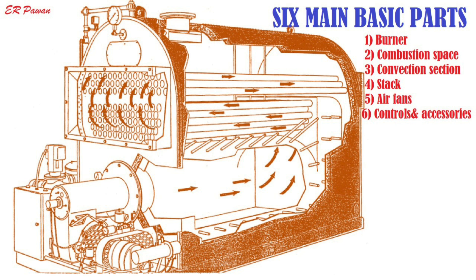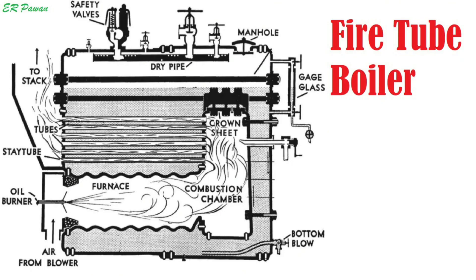Let's start with the fire tube boiler. Hot flue gases flow inside tubes that are submerged in water within a shell, where pressure is up to about 10 bar, producing up to 14 tons of steam per hour. It can meet wide and sudden load fluctuation because of large water volumes and is usually rated in HP.